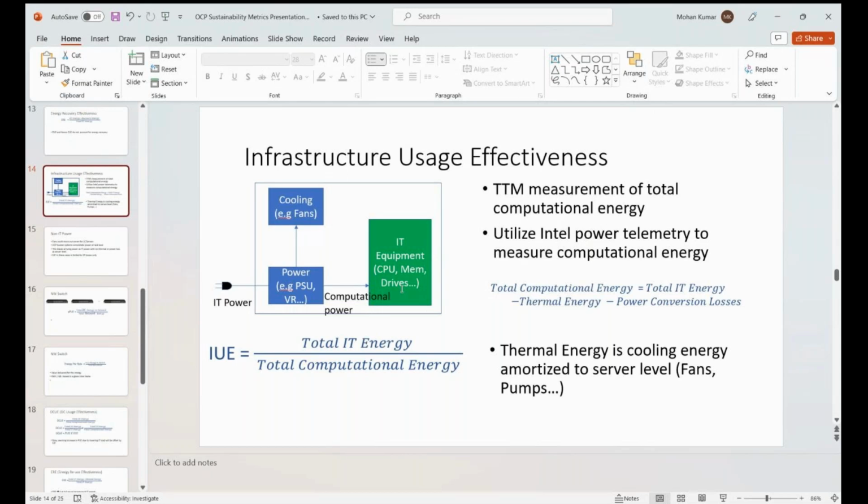But there are some cold plate direct-to-chip networking switches, from what I understand. Cold plate is qualified because it doesn't change the characteristics that much, right? So the fan should get reduced in that case. You would hope. But in general, switch silicon, they don't do a whole lot of qualification. This is our problem, right? This is not just the SAMI work group, but an overall sustainability issue. Networking guys are not that motivated to look at power. It's mostly about performance, so changing that mindset is going to be an uphill task.